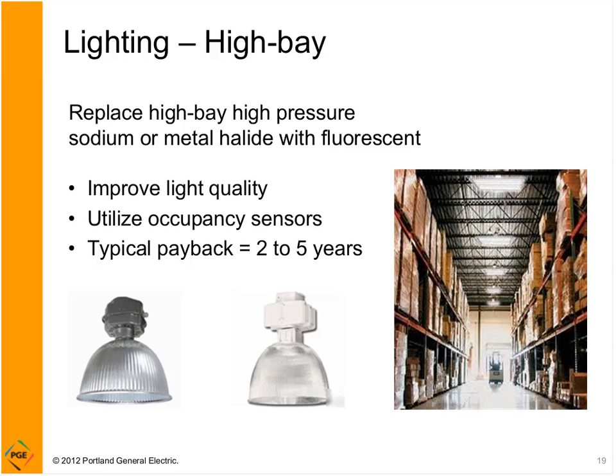So you can replace these with a fluorescent fixture, and that's represented in the photograph to the right. Basically, these are fixtures with 4-foot tubes in them, kind of enclosed fixtures. They can have as few as a couple lamps to 6 or more lamps. It kind of depends on the wattage of the existing metal halide. One of the things you're going to do when you replace the metal halide or high pressure sodium with fluorescent is improve the light quality. The color rendering index that I mentioned earlier in the fluorescent example is going to be much improved going from high pressure sodium or metal halide to fluorescent as well.